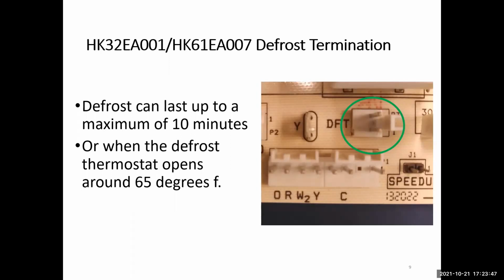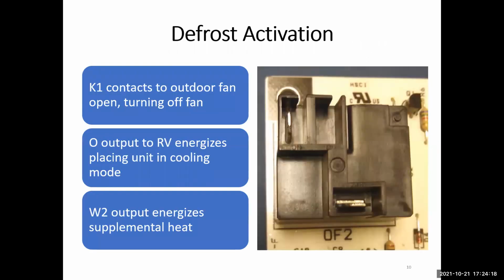Different units are designed to require different temperature activation and termination set points. For this reason, always consult your part selection program to assure the correct sensor is selected when replacing the sensor. Your defrost can last up to a maximum of 10 minutes, or when the defrost thermostat opens around 65 degrees. The outdoor fan relay is designed for a maximum current of 5 amps at 240 volts. This is a normally closed set of contacts, which opens when defrost is activated.